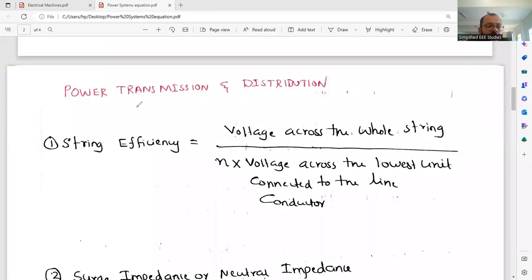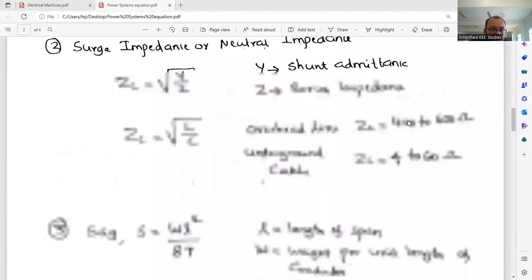Next, I would like to discuss some equations from transmission and distribution. In that, string efficiency is very important. Whenever you are placing the insulators, how do you calculate the string efficiency? The voltage across the whole string is divided by the total number of insulator discs used, multiplied by the voltage across the lowest unit connected to the line conductor. This is the formula for calculating the string efficiency. You have to remember this point.